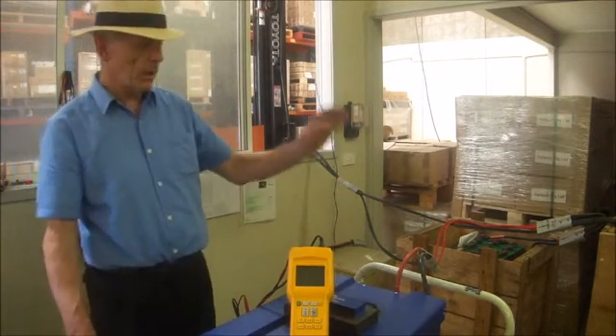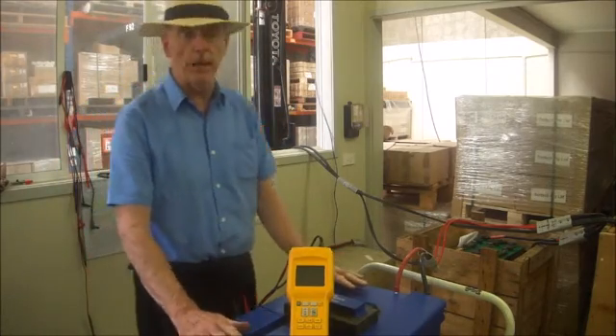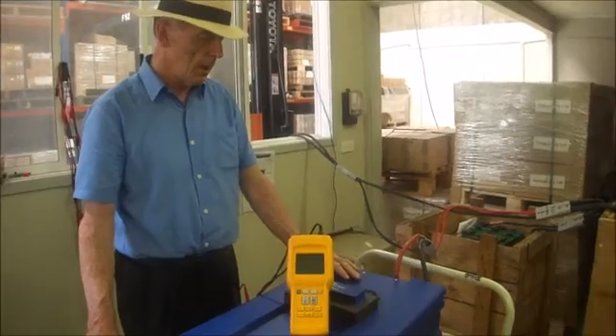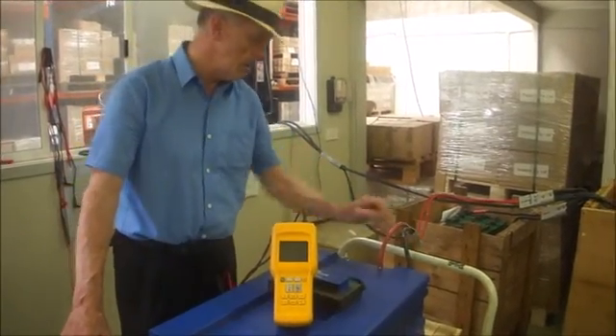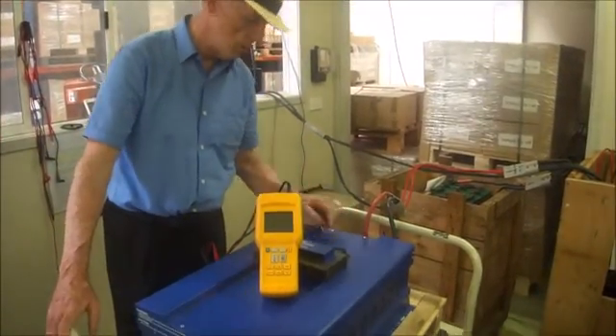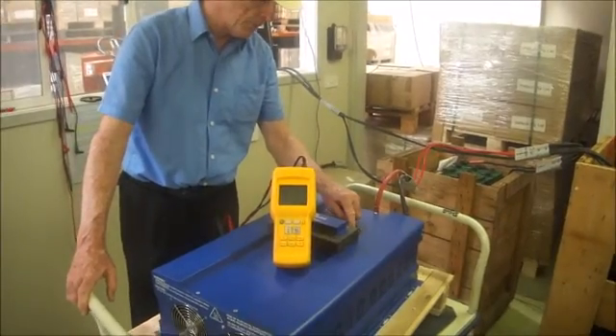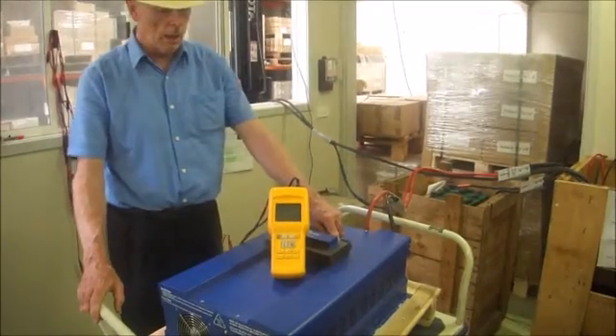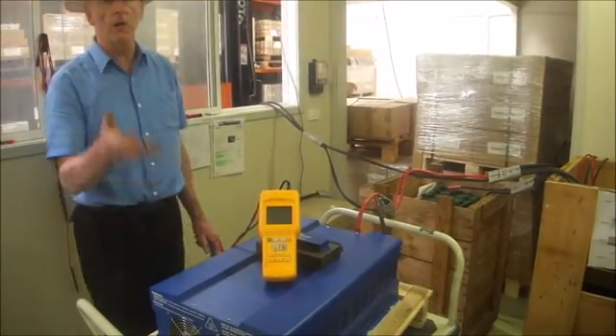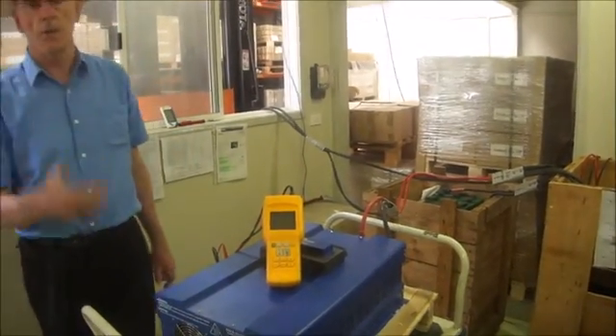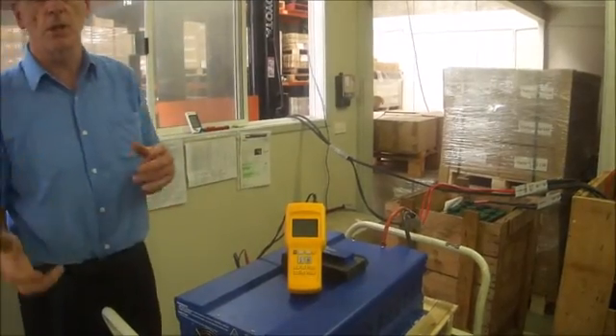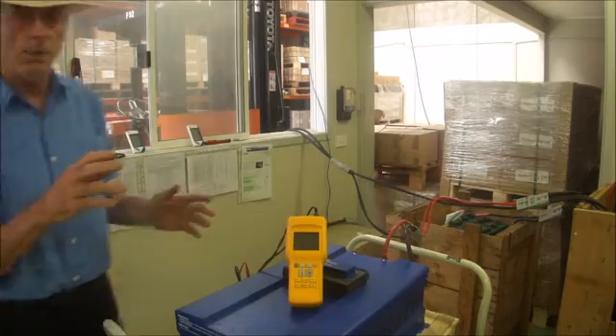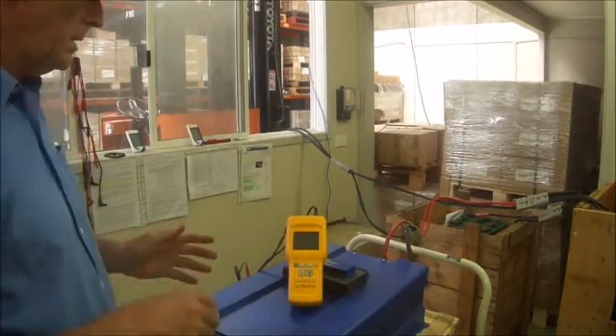So what we're going to do, we're going to turn this inverter on and we're going to have a look at it and see how good or how bad it is. The DC is connected and we'll turn it on with the power saving mode off. We'll go direct online and then we'll gradually increase the load and just watch the harmonics on the voltage and the current, and you'll be able to see the cleanliness of the waveform.